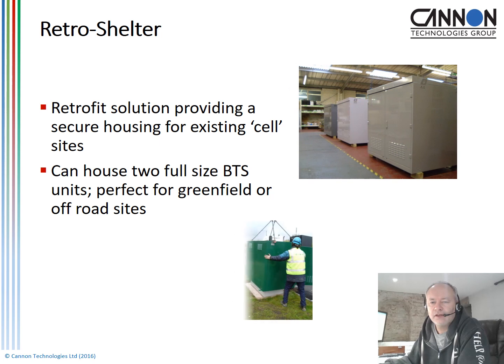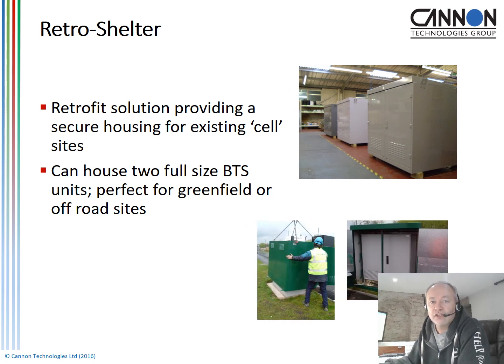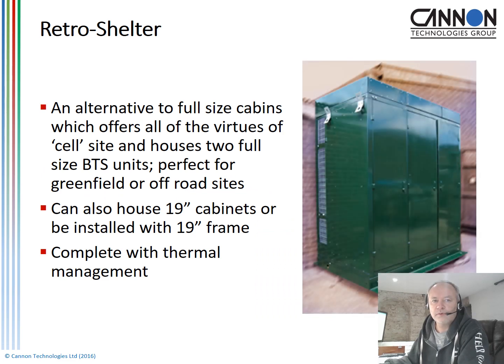Some additional products you can see here that Cannon manufacture based around outdoor cabinet applications is a retrofit shelter. These were developed specifically for mobile communications, where they've installed third-party outdoor cabinets which don't have a high degree of security, and in specific areas vandalism was a major problem, and Cannon developed this retrofittable shelter which is craned into position from above the cabinet. It still provides all the necessary cooling to the outdoor cabinet that's housed inside the shelter, but it provides a higher degree of security protection. Other examples are what we call a retro shelter. This is a larger outdoor shelter which could house standard indoor 19-inch racks. You can walk inside these units, and they would include all the thermal management to maintain an operating temperature for the equipment being installed.